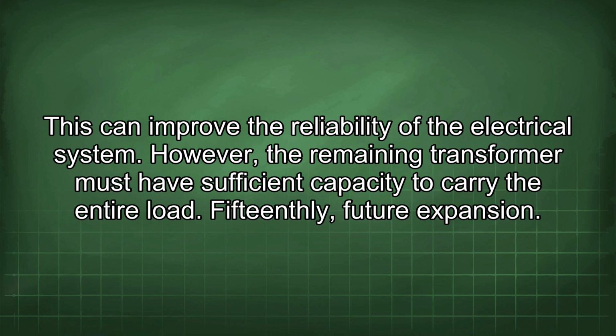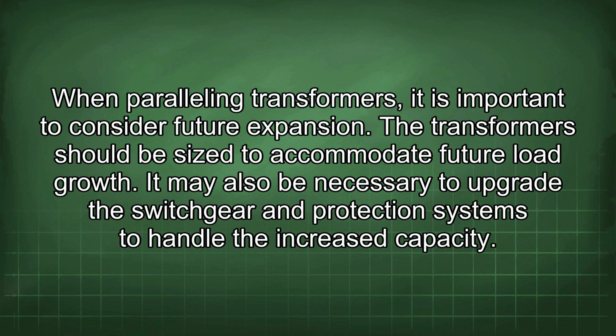Fifteenthly, future expansion. When paralleling transformers, it is important to consider future expansion. The transformers should be sized to accommodate future load growth. It may also be necessary to upgrade the switchgear and protection systems to handle the increased capacity.